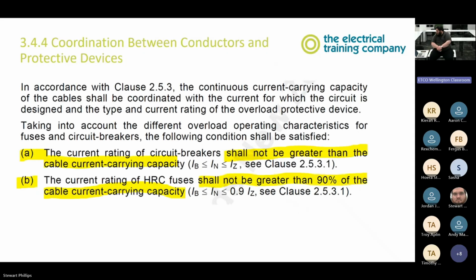So 3.4.4, coordination between conductors and protective device. So the current rating of the breaker shall not be greater than the cable current capacity, and the rating of the HRC fuse shall not be greater than 90% of the cable current carrying capacity. Why does the HRC fuse not be greater than 90% of the cable current capacity? Why might this be the case?